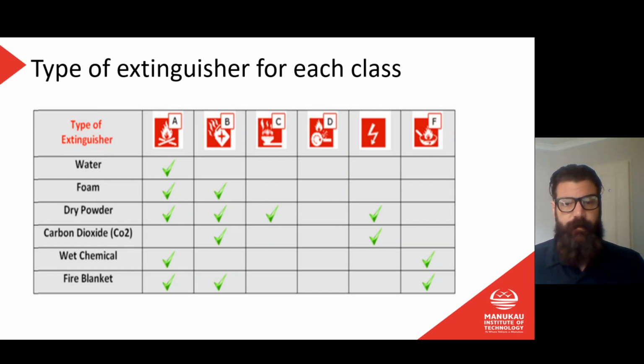For our gas fires, we only want to use the dry powder. For our metal fires, looks like we're out of luck. None of these, we do not have any fire extinguishers in normal circulation that are appropriate for use on metal fires. Electrical, we want to use dry powder or CO2, and then for the cooking fires, it's either wet chemical or fire blanket.